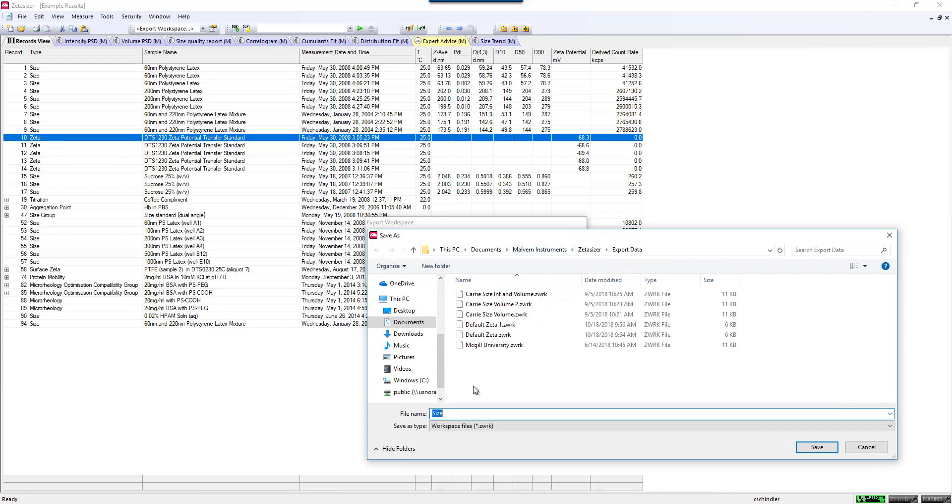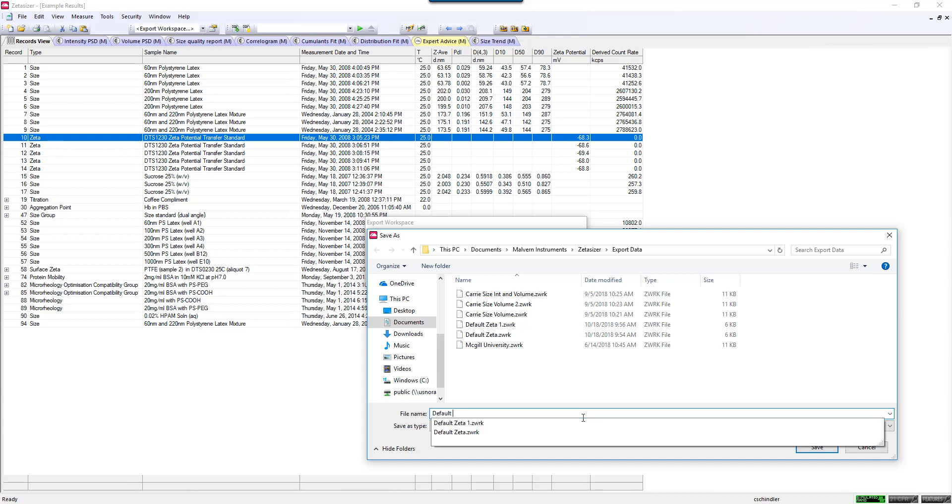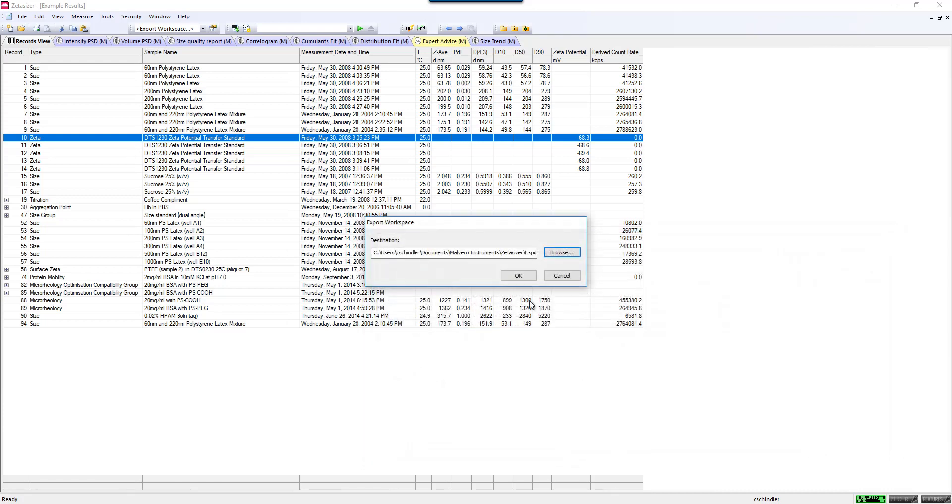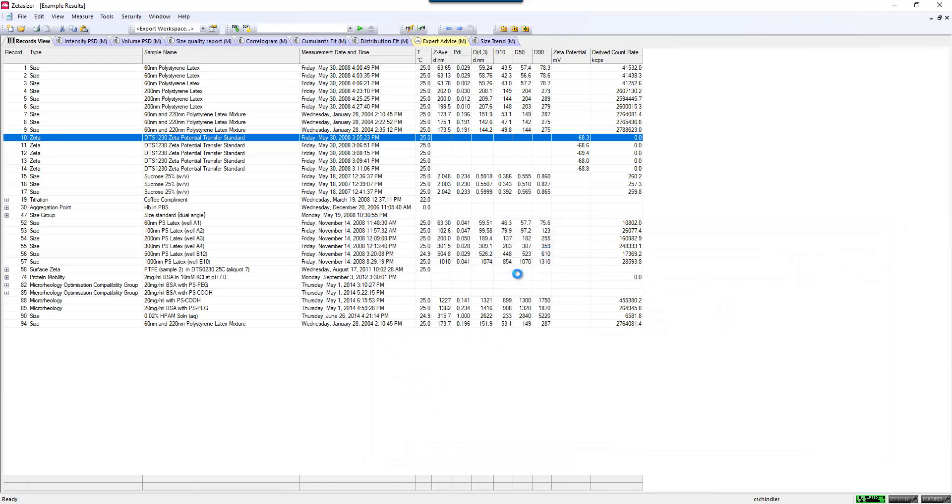What I would recommend is what you first do before anyone uses the system is go into these workspaces and save them somewhere as the default workspace. So let's say I'm on this sizing report, this is the default sizing report, and I want to export that workspace. Go ahead and save it in some sort of location. I like to save mine in this export data folder, which is defaulted in the Zetasizer software, and give that a name. So I'm going to call this default size and save that. That way, this never disappears. You can always go back and put it back into the software and have it defaulted just the way it was.